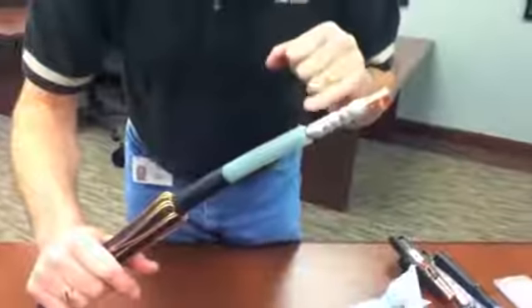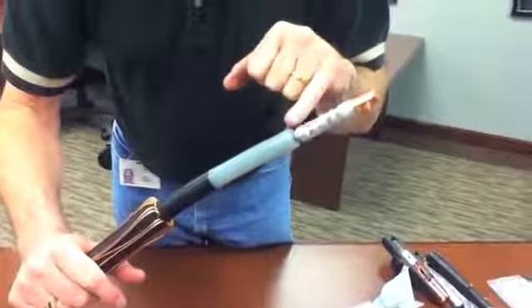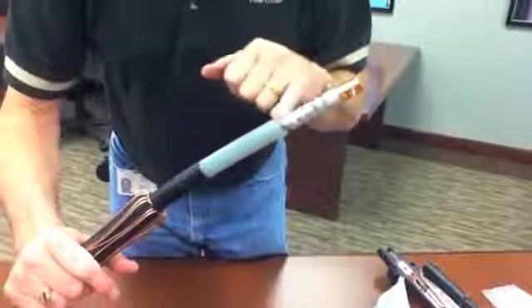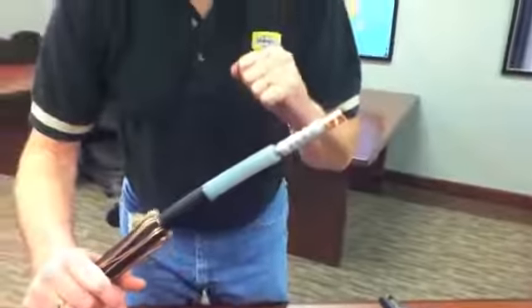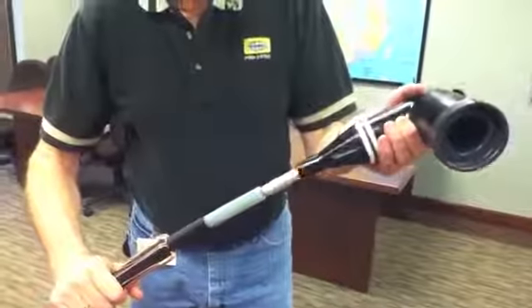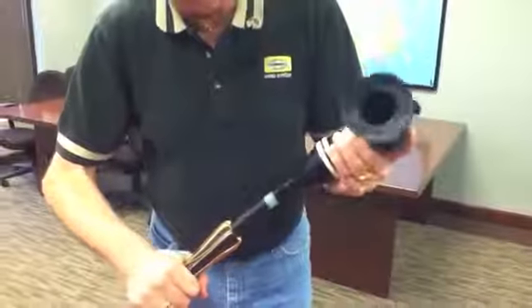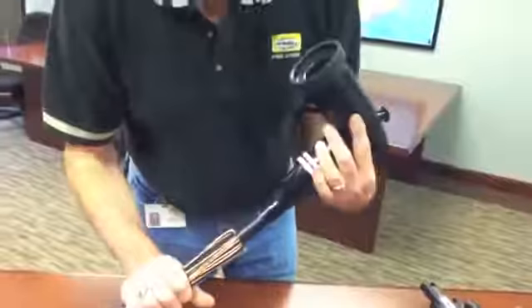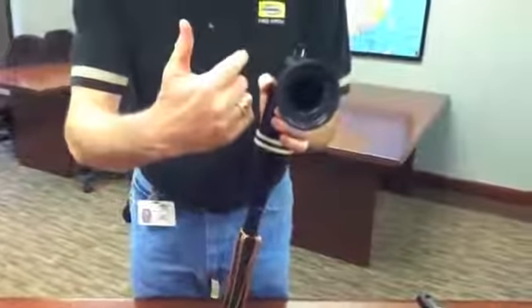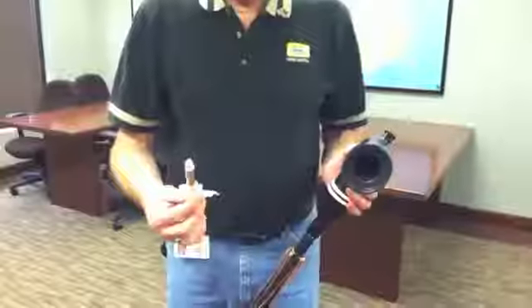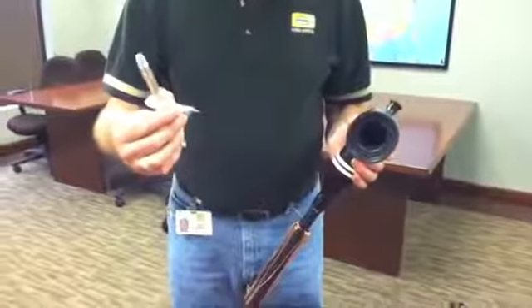We recommend that the end of the insulation is beveled no more than 1/8 of an inch back on approximately a 45-degree angle. We've now beveled the end of the insulation and we will relubricate and assemble it again. Going to install the elbow onto the cable with a slight back and forth twisting motion. As you can see, the elbow slides on a lot easier, and you will continue until the spade contact aligns with the elbow. The next step would be to assemble the load break probe.